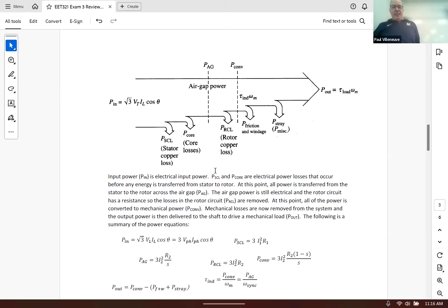That's where you calculate power. Here's a bunch of equations, you can take a look at them, they're pretty basic. The whole reason why we have all these equations is to show you that for every unit of power that crosses the air gap, 1 minus S units of power is converted power, converted to mechanical. The S ratio of that power that gets converted is lost to heat. So hopefully you can see the lower the slip, closer to zero, the more efficient the motor operates, because more power gets converted than is wasted as heat. But you're welcome to write these equations down, hopefully these are pretty self-explanatory.